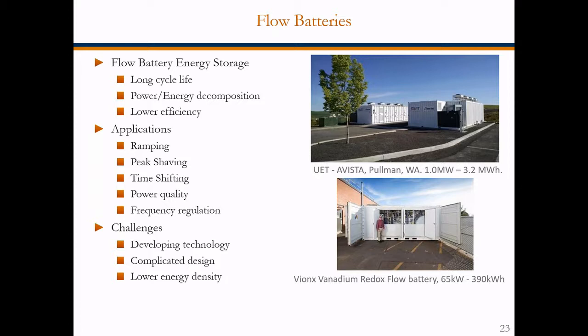The efficiency is much lower, as you saw in the chart earlier, like about 40 watt hours per kilogram. The applications of a flow battery are basically everything a lithium ion battery can do, but there are trade-offs. For instance, if you want to use it for a frequency application where it's on-off, the pumps need to be running all the time more or less, and that decreases your efficiency.